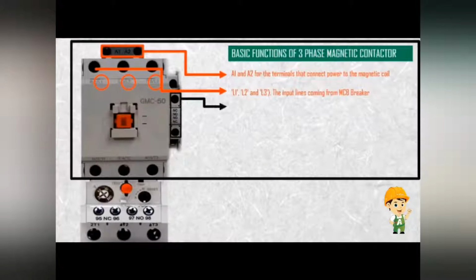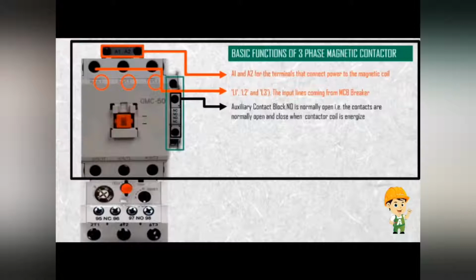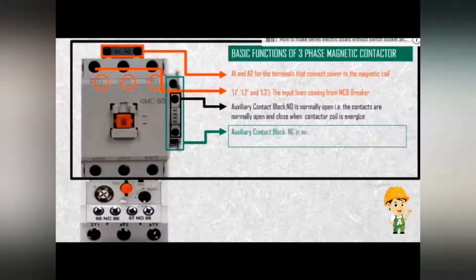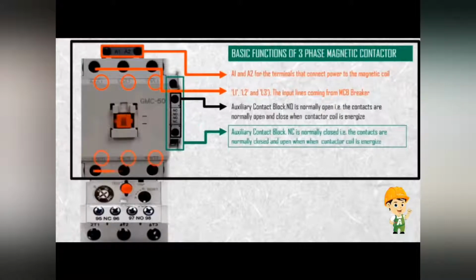The terminals on the right side are the auxiliary contacts. NO means normally open, which will close when the coil is energized. NC means normally closed - it will open when the coil is energized. The terminals at the bottom, marked T1, T2, and T3, are the outgoing terminals, which are the output side.